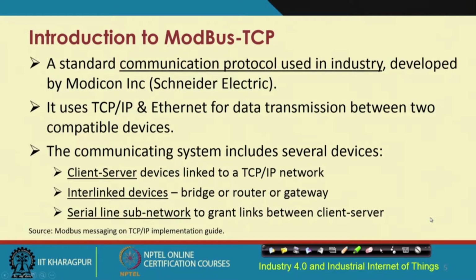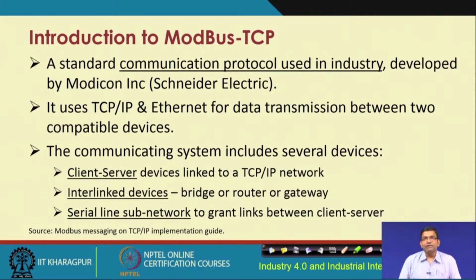As the name suggests, Modbus TCP is built on top of the TCP IP suite of protocols. So, it uses TCP IP and Ethernet for data transmission between different compatible devices. Compatible means that they have to talk the same language; both will have to use the same protocol, and only then can the communication happen. So, the TCP IP suite of protocols is used, and on top of that Modbus is used. So, you have TCP IP Ethernet and Modbus TCP built on top of the existing TCP IP Ethernet protocols.